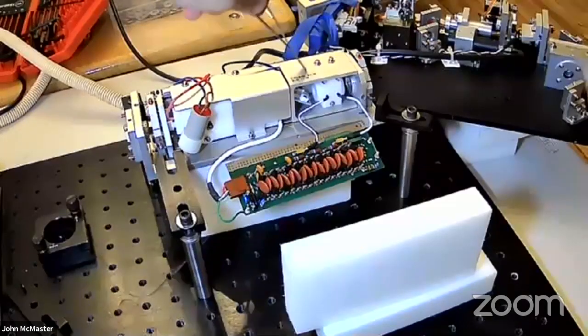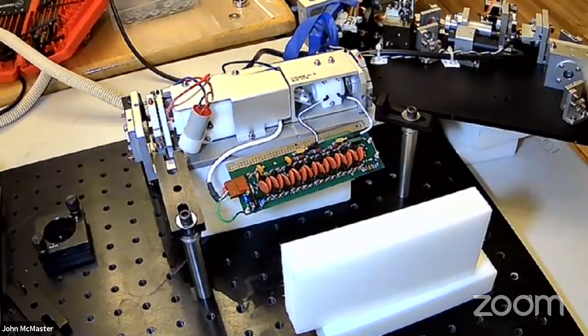Yeah. So the idea is just remove all of this stuff in here that you don't need initially, and just get the laser cavity firing in that very simple state. And that gives us at least a basic alignment. And then what happens is every time we add a new optical element to the system, it very slightly distorts the beam path. And then we can correct the beam path after adding that new element.